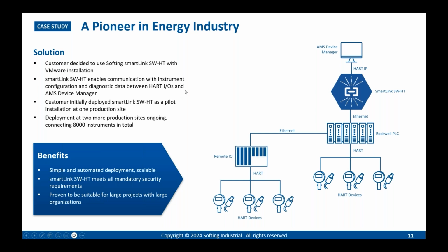As it was a pilot project, they initially deployed and tried it for 600 devices, and then we are in the process to implement at 3 different sites and connect more than 8,000 instruments. What I see in the next 1 or 2 years is that it would probably be more than 100,000 devices that could be connected via the SmartLink solution to AMS Device Manager.